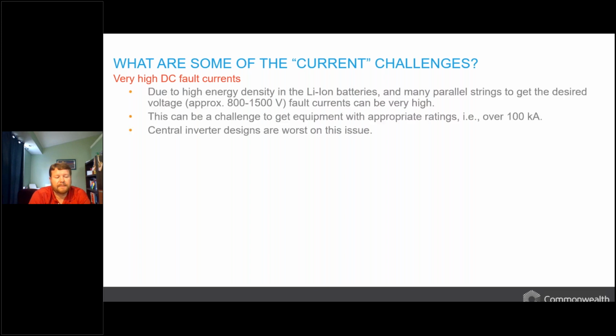So, talking about some challenges, these are some of the current challenges that we experience when we're doing electrical studies for our battery energy storage systems. The first challenge is very high DC fault currents. To get the energy density required for lithium ion batteries, we're limited on our voltage. On the DC side, we're limited to somewhere between 800 and 1500 volts, and that's really based on the inverter manufacturers themselves. The inverters on the DC side don't want to allow too high a voltage because it requires the inverters to get larger and more expensive, mostly because of the added insulation required inside the equipment.